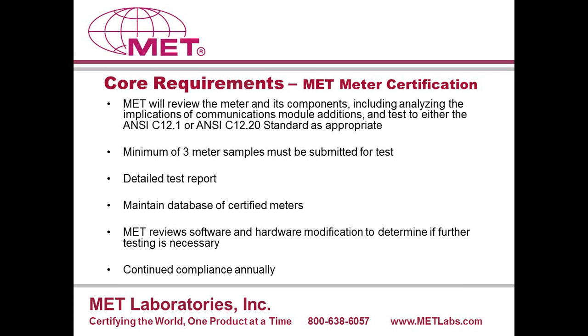Utilities and buyers of these electricity meters all want to see the ANSI set of criteria met, whatever is applicable. Typically, everything that's applicable would need to be tested before they would go ahead and purchase a product from a manufacturer. But there's a separation of sorts between manufacturers that have been in the business for a while and have established relationships with utilities in certain regions, and those manufacturers that are trying to break into the marketplace. So really the MET meter certification program can be helpful to everyone, but it's probably most helpful for the new manufacturers trying to break into the marketplace and establish relationships with the utility.